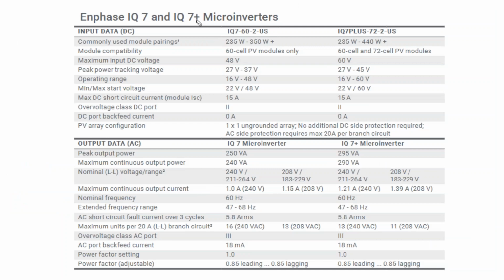But as far as the microinverters go, it's one microinverter per solar panel. So if you have a 60 cell residential solar panel, you use the 60 cell microinverter, and it's compatible with pretty much any 60 cell module. One common mistake, I just caught at the end of last year. A solar company sold some material to a customer using old solar panels and old microinverters, and their funky old solar panels turned out to be residential sized, but they were 72 cell panels, and they were putting them on 60 cell microinverters. So without even knowing the spec sheets or the actual specs, it's like, no, those aren't compatible, or probably not going to be compatible because they're not in the same kind of category.